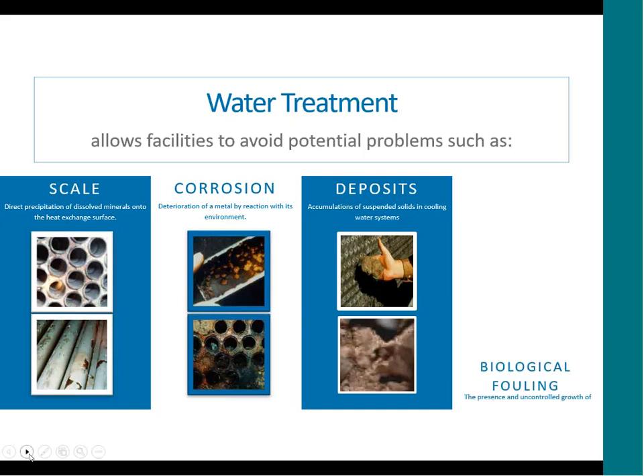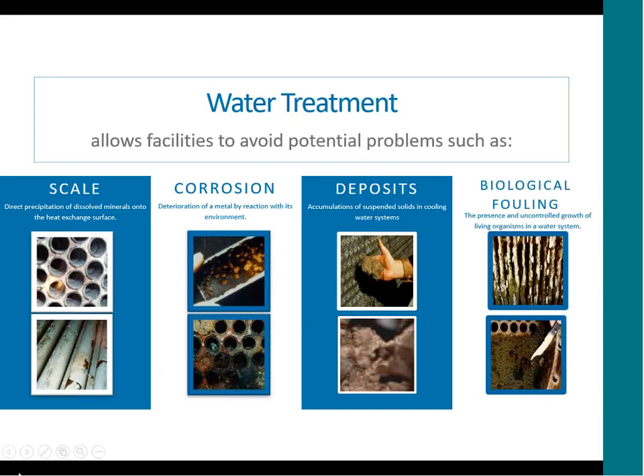Another issue that we have is biofouling, and that's the uncontrolled growth of microorganisms in a water system. It can be bacteria, it can be algae, any kind of microorganism that can grow and proliferate in the water system. The water systems are usually warm water, moist, and open to the atmosphere so they can get contaminated. They are a good breeding ground for bacteria. I like to think of it as a giant petri dish. Our deposits can be a bacteria food source, so they all kind of intermix together. But with biofouling, we can get slime.